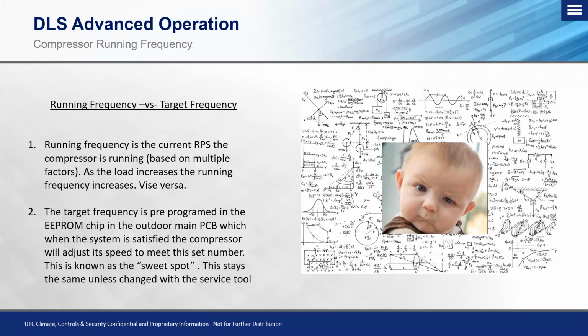Okay, as they draw closer to set point, we're going to have our running frequency slow down or decrease. And again, like we talked about with the running frequency, as the load decreases, the running frequency decreases. As all of those units start to get closer to their set points, the system is now going to look at the target frequency to run the compressor.